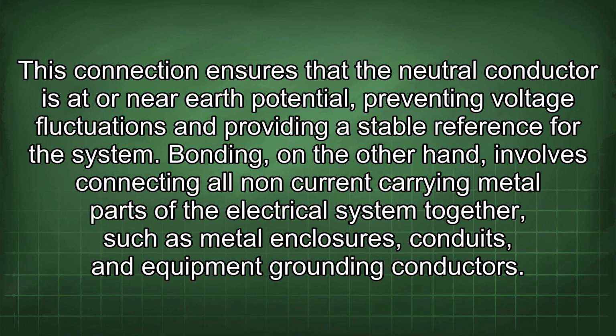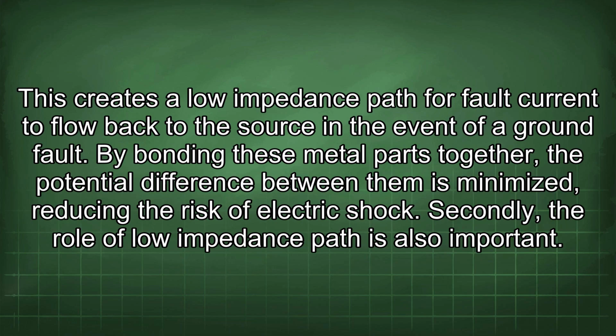This connection ensures that the neutral conductor is at or near earth potential, preventing voltage fluctuations and providing a stable reference for the system. Bonding, on the other hand, involves connecting all non-current carrying metal parts of the electrical system together, such as metal enclosures, conduits, and equipment grounding conductors. This creates a low impedance path for fault current to flow back to the source in the event of a ground fault.